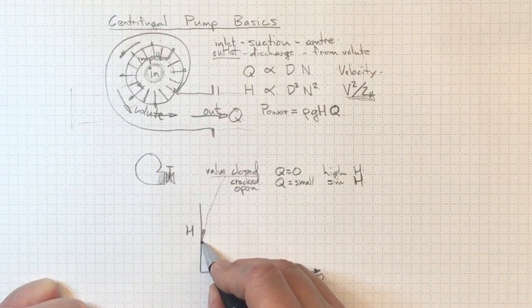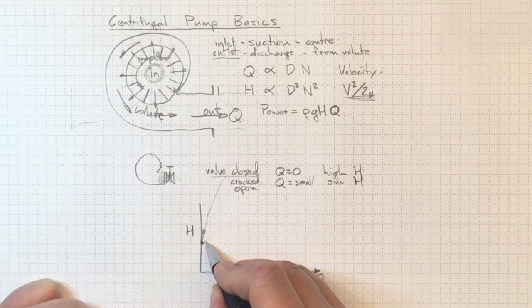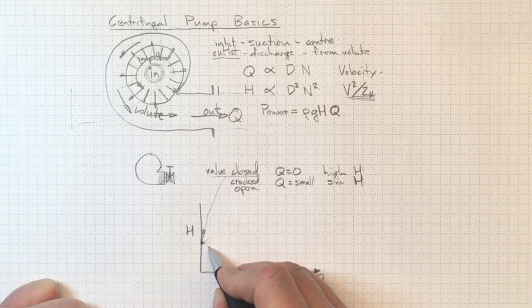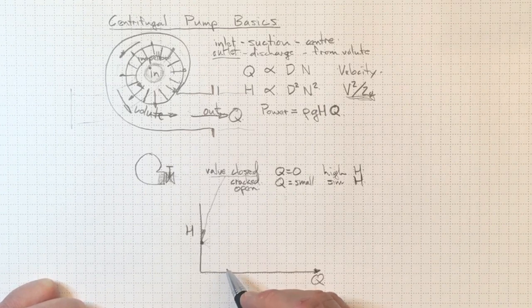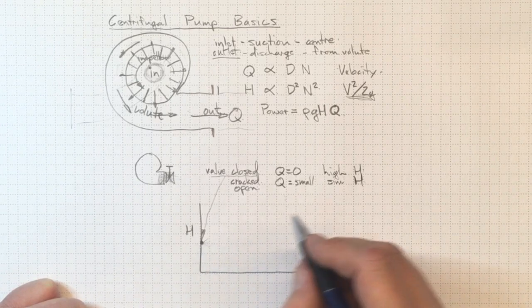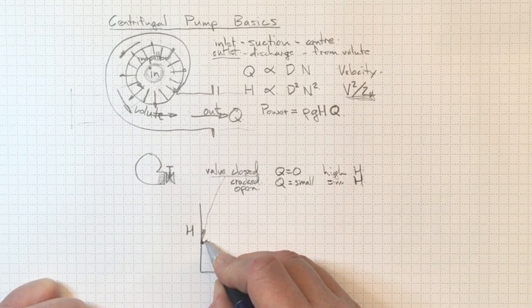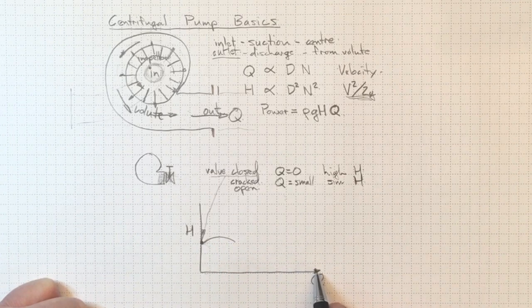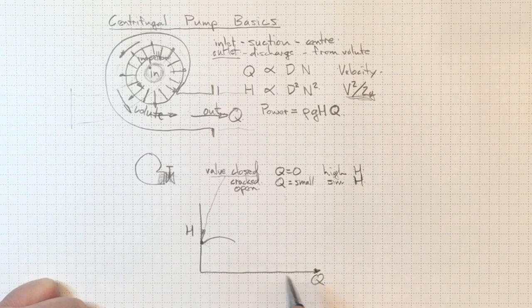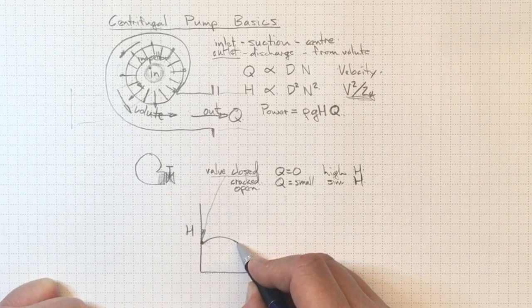And depending on the geometry and details of exactly what's inside the pump, we may see the head actually increase or stay the same or possibly decrease, depending again on the geometry and the details that you can figure out more about in a turbo machinery course. Let's say it increases. We'll hit a peak, but eventually the head is going to be decreasing as we have increasing flow.